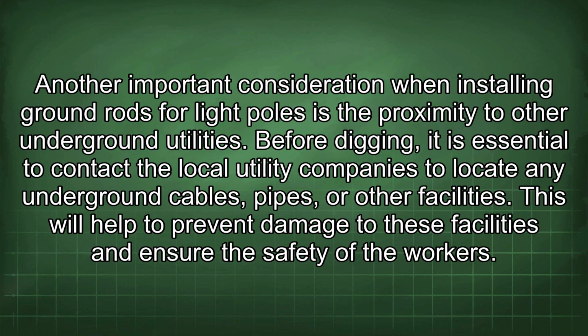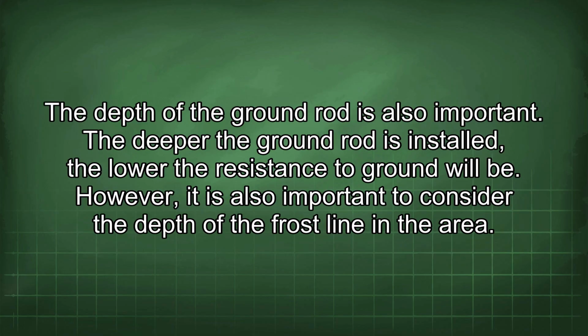Another important consideration when installing ground rods for light poles is the proximity to other underground utilities. Before digging, it is essential to contact the local utility companies to locate any underground cables, pipes, or other facilities. This will help to prevent damage to these facilities and ensure the safety of the workers. The depth of the ground rod is also important. The deeper the ground rod is installed, the lower the resistance to ground will be.